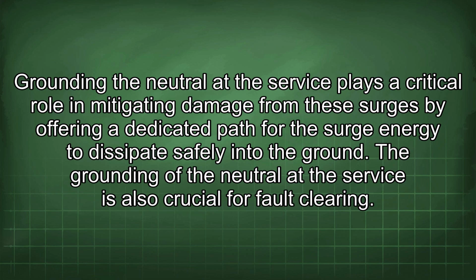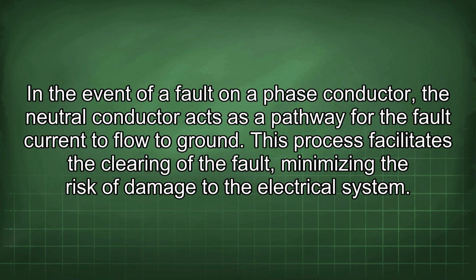The grounding of the neutral at the service is also crucial for fault clearing. In the event of a fault on a phase conductor, the neutral conductor acts as a pathway for the fault current to flow to ground. This process facilitates the clearing of the faults, minimizing the risk of damage to the electrical system.